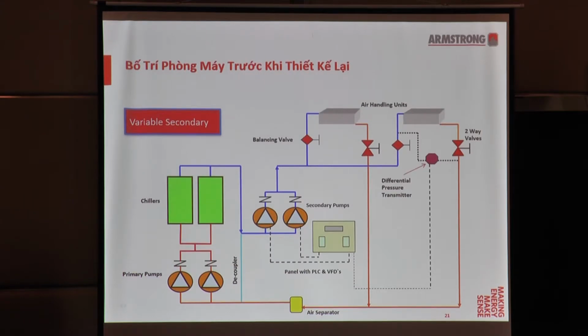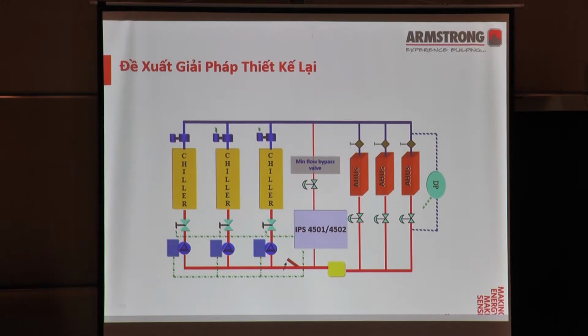So what the plant looks like before the redesign is variable secondary, right? Here's the chiller and there are the primary and secondary pumps. You've seen this before in some projects. Nothing spectacular. But when we re-proposed our Armstrong solution with a new design, you can see the pumps attach directly to the chillers. And this is simplified as well with our IPS 4502 controls.